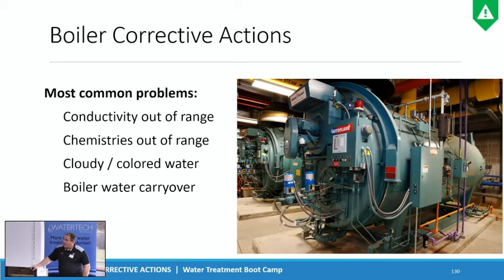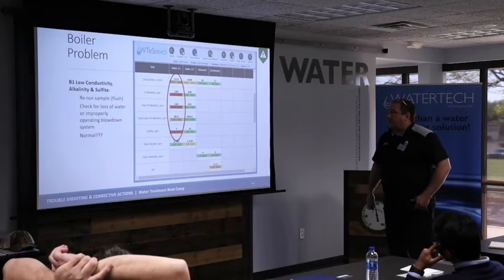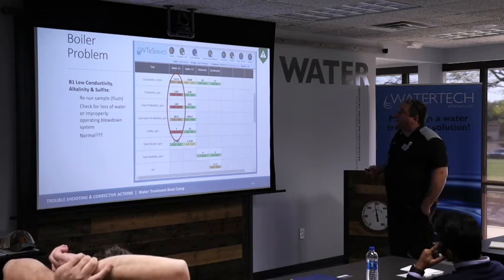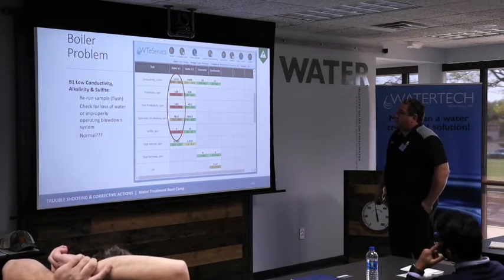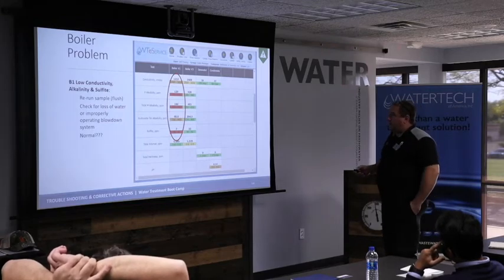And then the other one is boiler water carryover, where literally the water that's in the boiler makes its way into the steam header itself and it just carries itself over into the steam system. So this is where we're going to show you some tests that were actually done at a customer's location. We're going to blame Jeff for all this because it was his customer. So you run a test, boiler one.